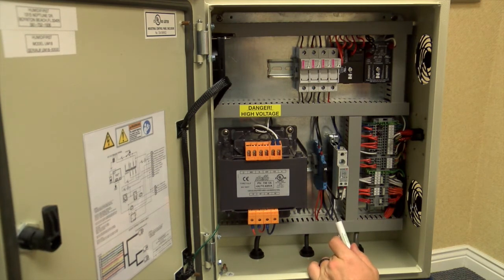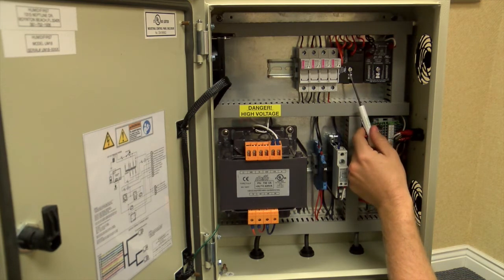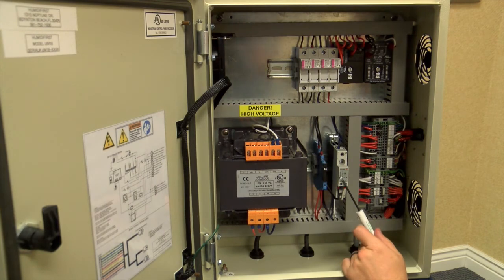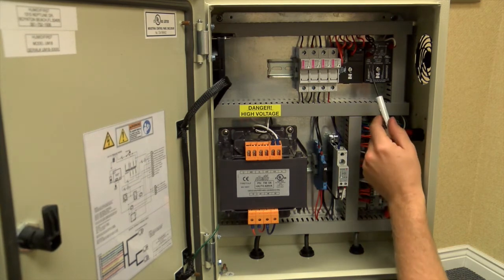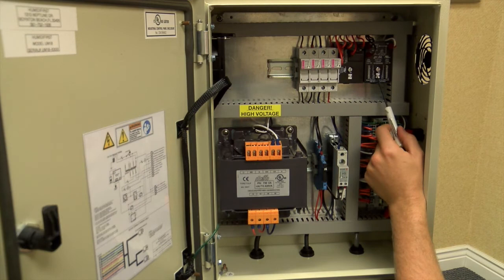Located right here is your R1 relay. R1 controls your low water safety, water level maintenance, and can be turned on and off via your humidistat. R2 is a time delay relay for your solenoid and float switch. R3 is a relay that controls your transducers. R4 is the time delay relay that says how long your transducers will stay on and off.